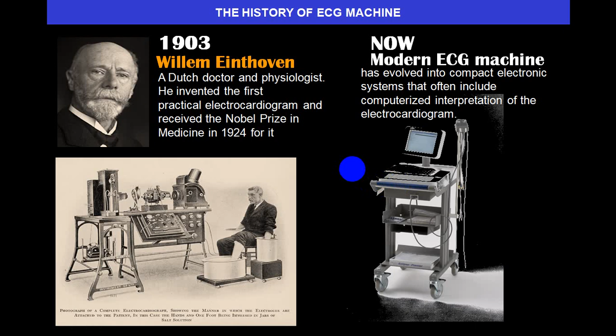Normally we have an ECG machine with 10 electrodes. 4 are for attachment to the limbs and 6 are for the 6 chest leads. Some ECG machines have only 5 electrodes, where 4 are for the limbs and 1 is for the chest electrode, which you will have to reposition as you go on changing the chest leads. And these are usually in a manual variety where a 5-electrode cable is utilized.